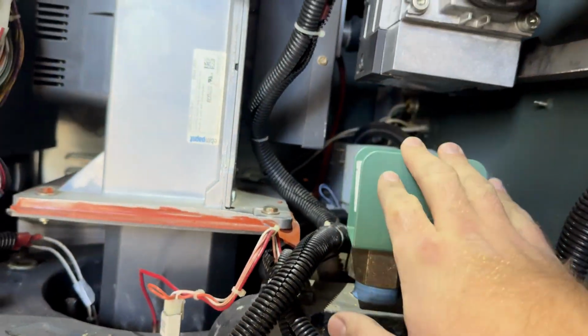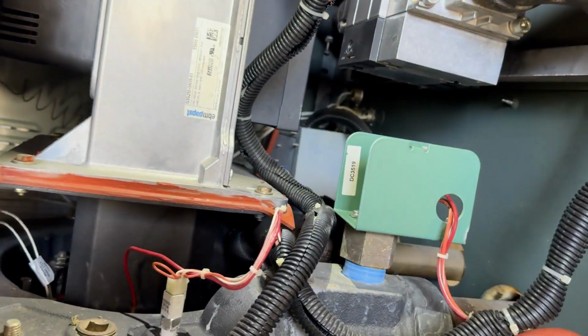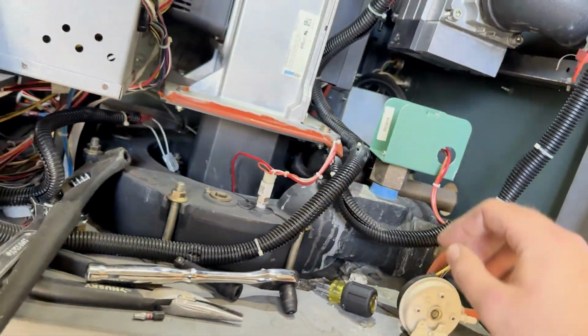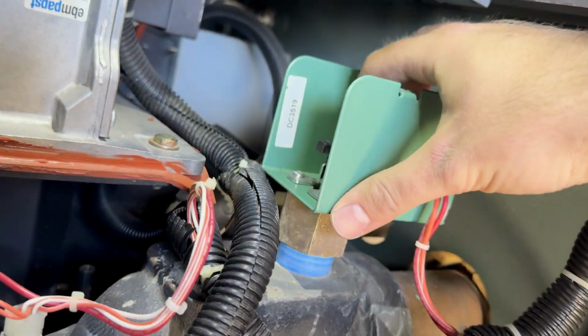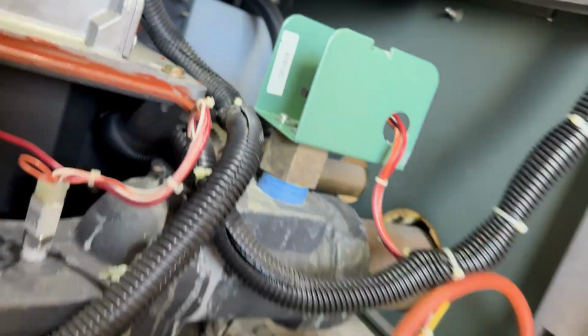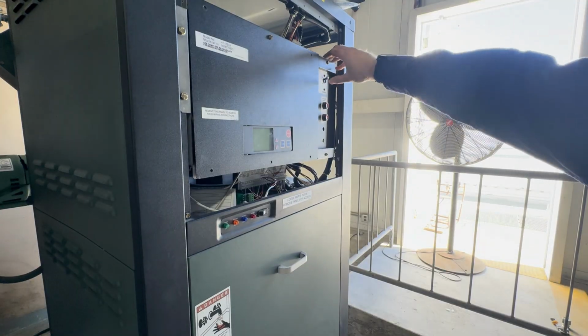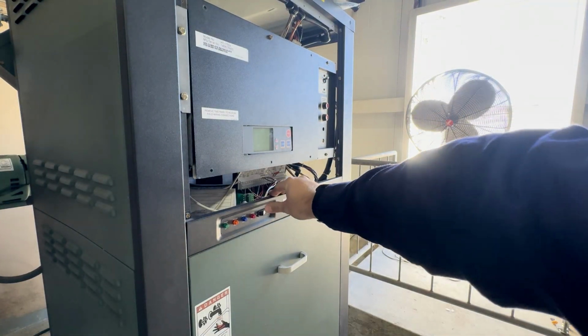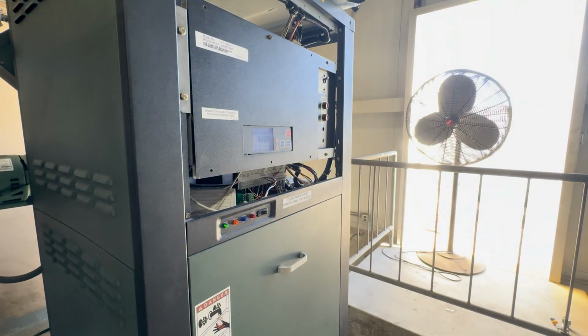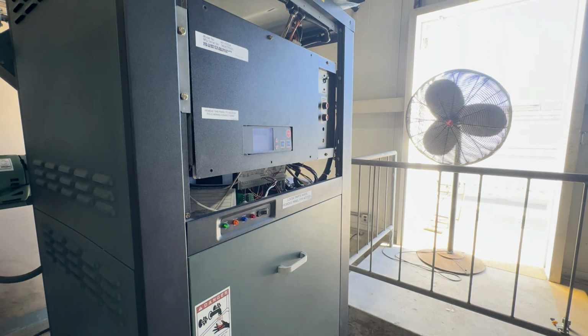We're gonna go ahead and turn the boiler on, test it, make sure this flow switch actuates properly. So we're gonna be looking for this action right here. And once that switch is made, and here on the control board, one of these fittings, I think it's the third one down, we should be getting a signal too. We got our lockout tagout removed from the disconnects. Turn the boiler back on.